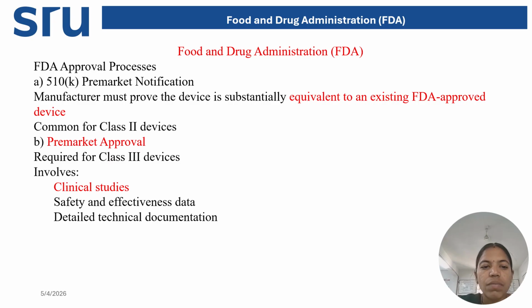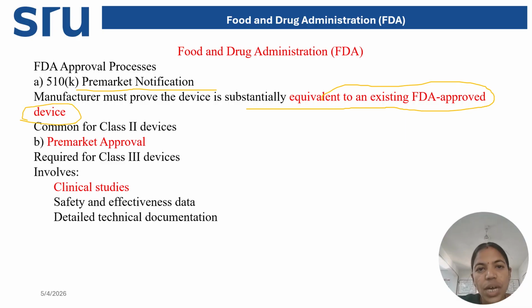So FDA approval needs pre-market notification, which means the device has to be substantially equivalent to an existing FDA approved device. Whenever you are bringing a new device, that device should be equivalent to an existing FDA approved device, and pre-market approval. For class 3, we compulsorily need the pre-market approval, for which clinical studies must be conducted. Safety and effectiveness data should be taken care of. Detailed technical documentation must also be prepared. Then only can we go for the FDA approval process.